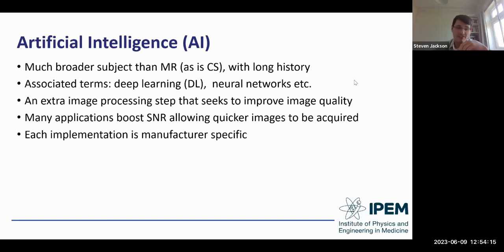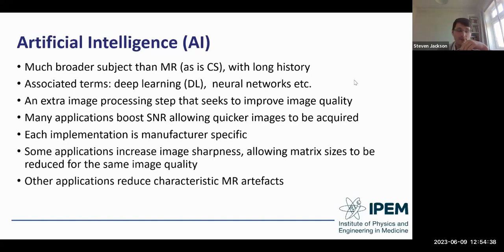In terms of the MR implementation, AI is an extra image processing step that seeks to improve image quality. Many applications boost SNR, allowing quicker images to be acquired. Each implementation is manufacturer-specific. Some applications also increase image sharpness, allowing matrix sizes to be reduced for the same image quality — with additional benefits of boosting SNR and reducing time. Yet more applications are designed to intrinsically reduce characteristic MR artifacts, so there are many side benefits coming along with AI reconstructions for improved image quality.